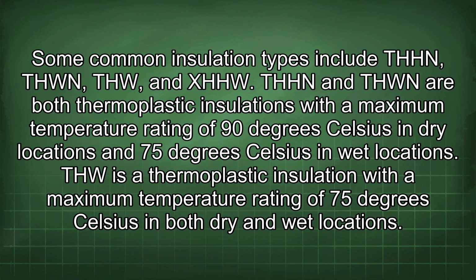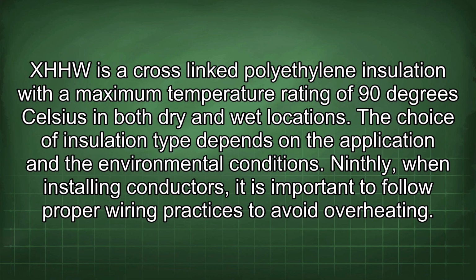THW is a thermoplastic insulation with a maximum temperature rating of 75 degrees Celsius in both dry and wet locations. XHHW is a cross-linked polyethylene insulation with a maximum temperature rating of 90 degrees Celsius in both dry and wet locations. The choice of insulation type depends on the application and the environmental conditions.